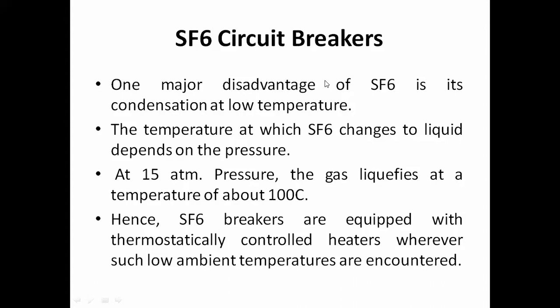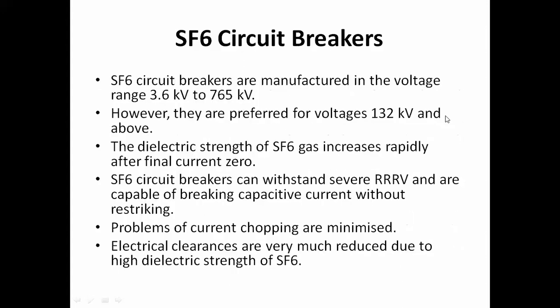And due to this, if SF6 circuit breakers are installed in cold areas, you also have to adopt thermostatically controlled heaters. So due to this, the cost of the circuit breaker somewhat increases. Okay, so this type of circuit breaker, that is the SF6 circuit breaker, is manufactured for voltages from 3.3 kV to 132 kV.